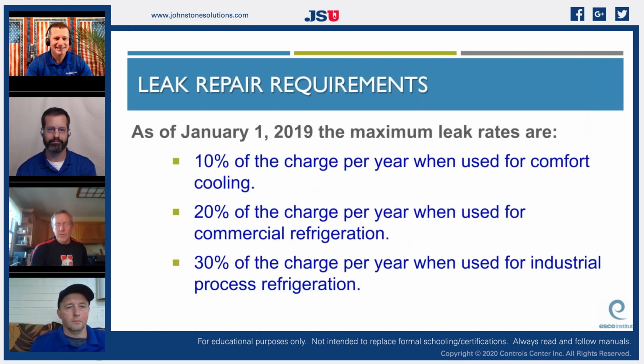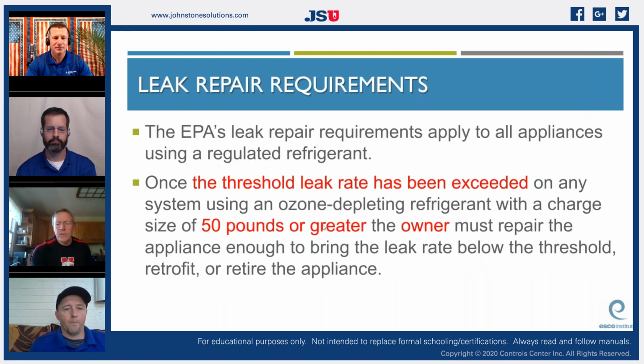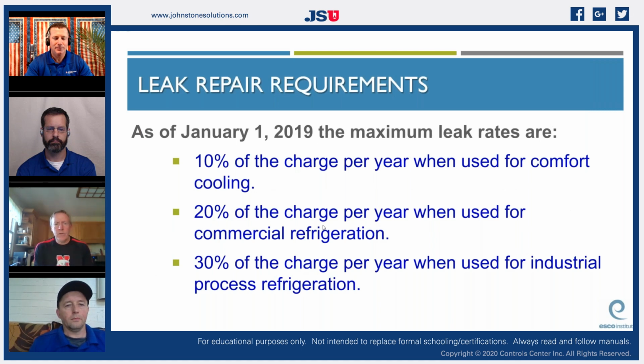That's right. And here are the actual rates for systems holding, again, over 50 pounds. That is 10% annually of the charge for comfort cooling. So if it's air conditioning, they consider it a luxury, and they give you the lowest leak rate possible. 10% for comfort cooling, 20% for commercial refrigeration, 30% for industrial process refrigeration, or 30% for a system that's used for more than 50% industrial process refrigeration. Those are all things that are, go ahead.